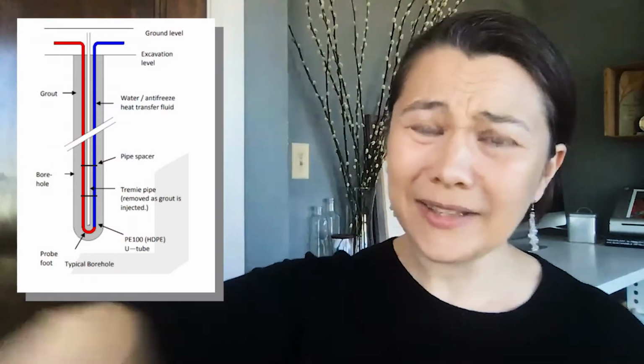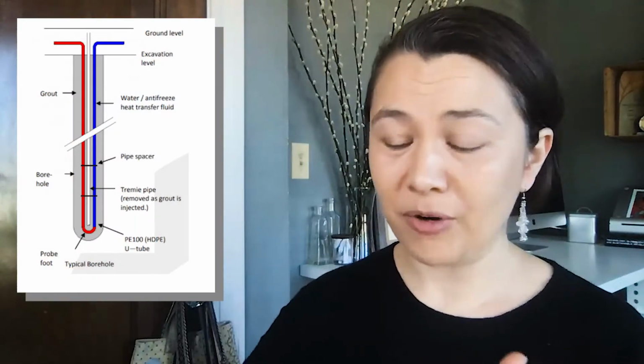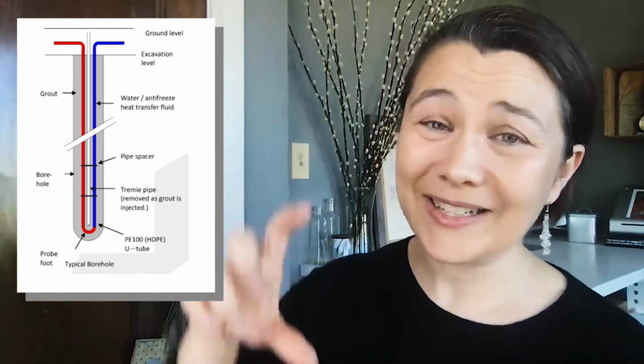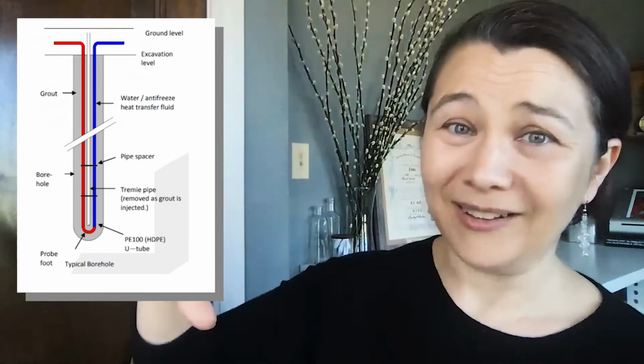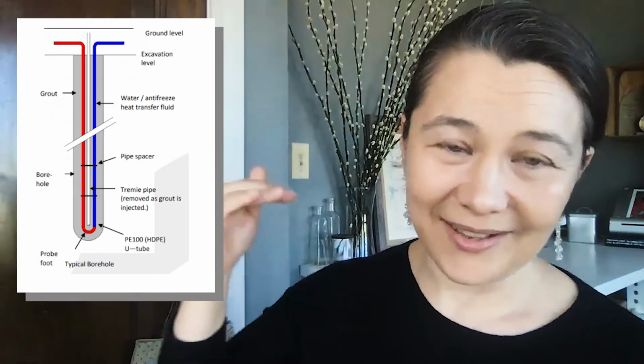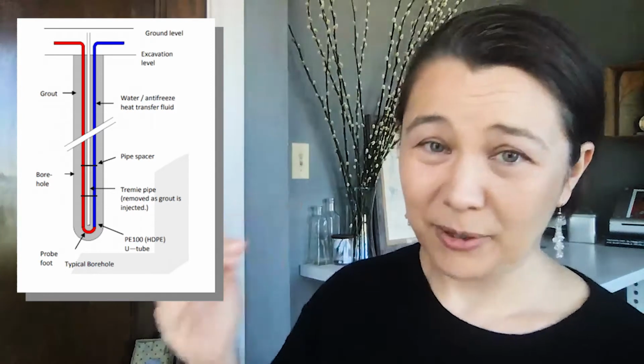There are closed-loop vertical geothermal boreholes in the street or other accessible places, brought on and off the system as needed to keep the loop temperature within a design window. That window is basically the perfect spot to keep the heat pumps happy, operating at maximum efficiency. The managing mechanisms are the borehole array, which stores energy over a year, and bringing sources and sinks on and off the system as needed — so you can evolve with a changing climate by adding more sources or sinks.